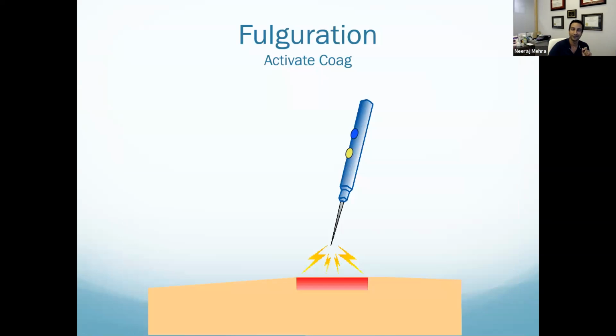So this is fulguration, if you use a coagulation mode. Now, you can do it with a high energy setting, but because it's a 6% duty cycle, instead of vaporizing the tissue, if you stay on one spot, it gives these bursts that are on and off. High energy over a short amount of time creates char on the top, which has high resistance to flow, and everything below stays completely raw and uncooked.